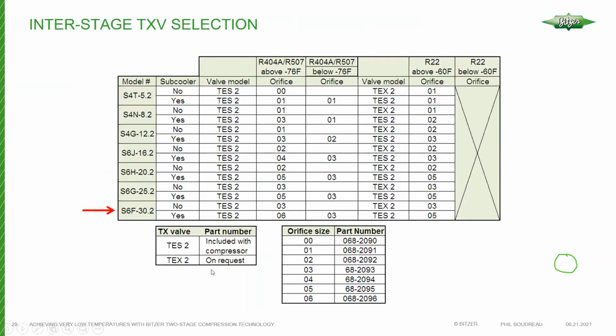Orifice selection is quite simple. We need to know the compressor model number, of course. We need to know the refrigerant. Are we using a subcooler? In this case, yes, we're going to use a subcooler. Let's say we're using a 404 or 507, and the application is above a saturated suction temperature of minus 60 degrees C or minus 76 degrees Fahrenheit. In this case, we would use an 06 orifice. Okay, so it's that simple.